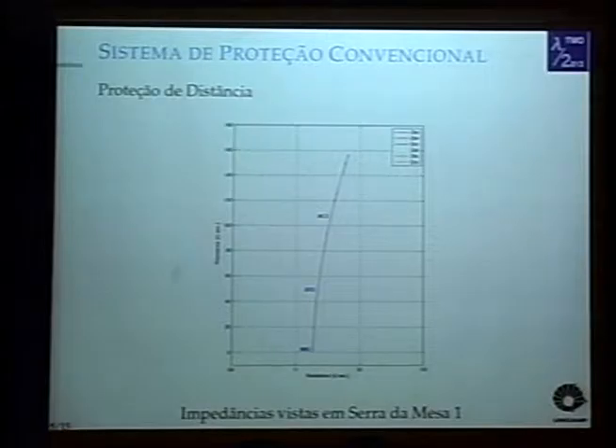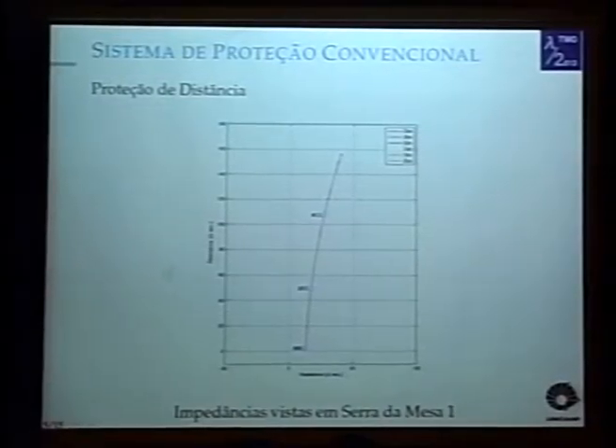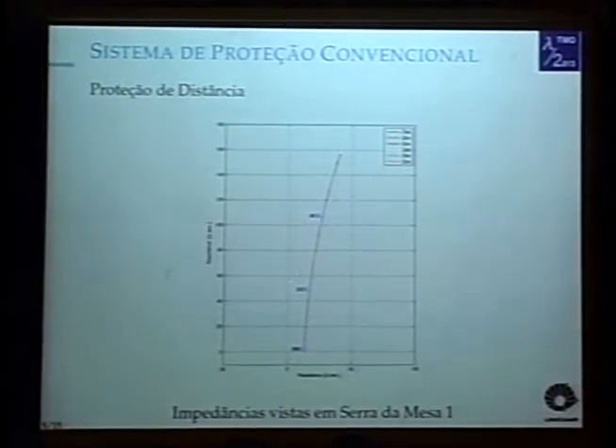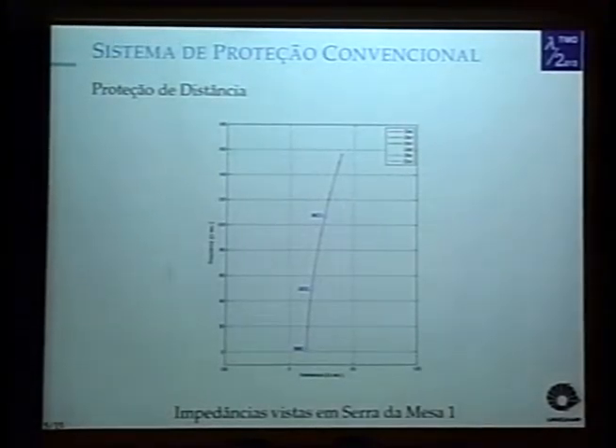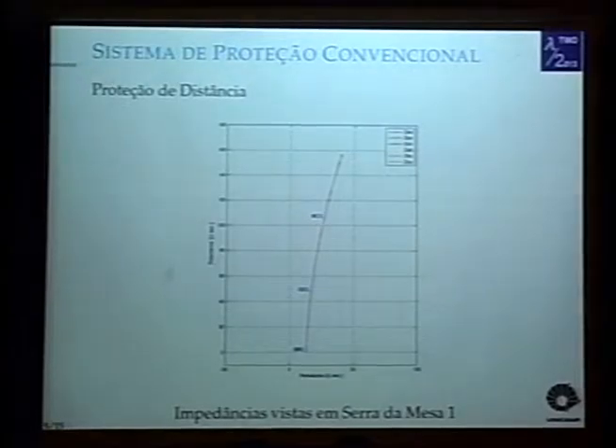So analyzing the conventional protection system, we have that the protection system in the substation of Serra da Mesa 1 was designed to protect the segment of line between Serra da Mesa and Gurupi with a primary protection system. And it should also supply backup protection for this segment between Gurupi and Miracema. And perhaps it also has a third area to protect, which is this other segment after the third substation.